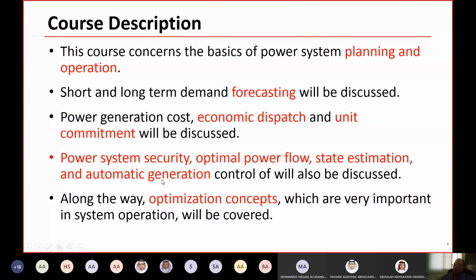So you have to take an appropriate action to remove this problem. The optimal power flow will also be discussed - real power flow and reactive power flow - and state estimation. For state estimation, you need to monitor your transmission line; with some measuring instruments, you can estimate voltage and angles at each bus in your system, so you can see whether you have over voltage or under voltage, or any problem. This is called state estimation.